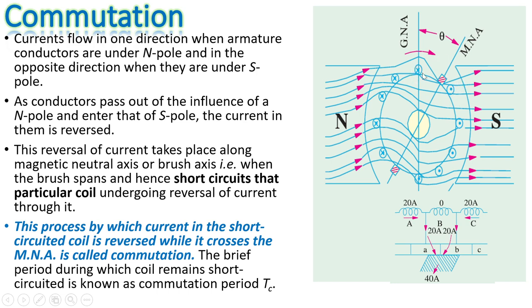As conductors pass out of the influence of the north pole and move under the south pole, the current in them changes direction — if the current was negative it becomes positive. This reversal of current takes place along the magnetic neutral axis or brush axis, when the brush spans and short-circuits the particular coil undergoing reversal. This process by which current in the short-circuited coil is reversed while it crosses the magnetic neutral axis is called commutation. The brief time during which the coil remains short-circuited is known as commutation time or commutation period tc.